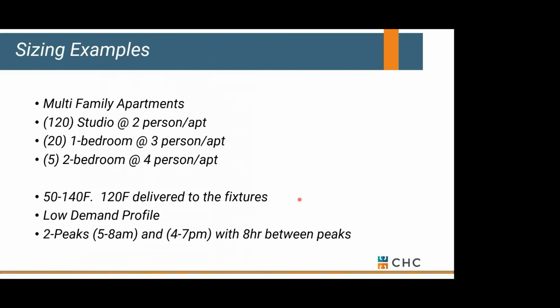All right, I've been mumbling along for a while, so let me get to my sizing example, which shouldn't take too long. But I just wanted to look at, all right, somebody throws a multifamily apartment at us with roughly 145 units inside this apartment building. For the life of me, I should have made this a 100-degree rise instead of a 90-degree rise, but all right, just bear with me. We're going to call this a low demand profile, and we're going to assume that there's 2 peaks throughout the day for domestic hot water use. Okay, one in the morning from 5 to 8, and another in the evening from 4 to 7, basically 8 hours between our peaks. That's really important when we get to our heat pump water heater sizing.